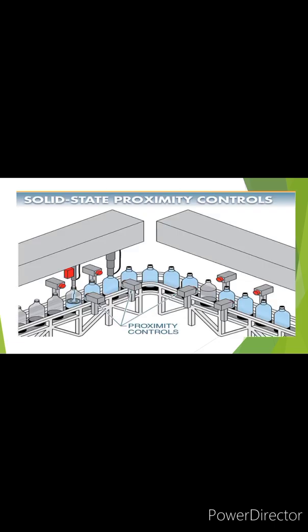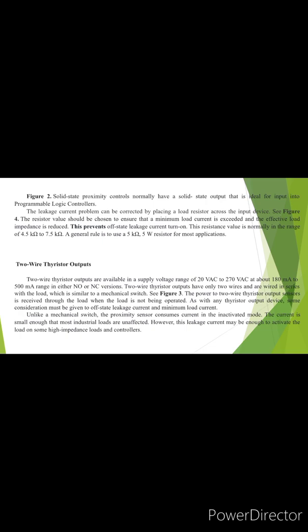Photoelectric control can be input into programmable logic controllers for detection, inspection, monitoring, counting, and documentation. Available outputs include 2 and 3 wire types with thyristor and transistor output that can be connected individually or in series or parallel combination. This is the figure, solid-state proximity controls. Figure 2. Solid-state proximity controls normally have a solid-state output that is ideal for input into programmable logic control.